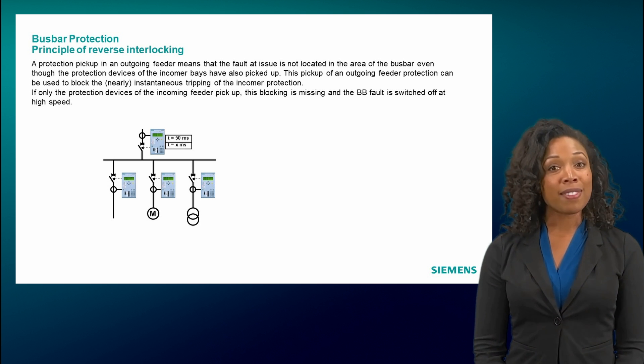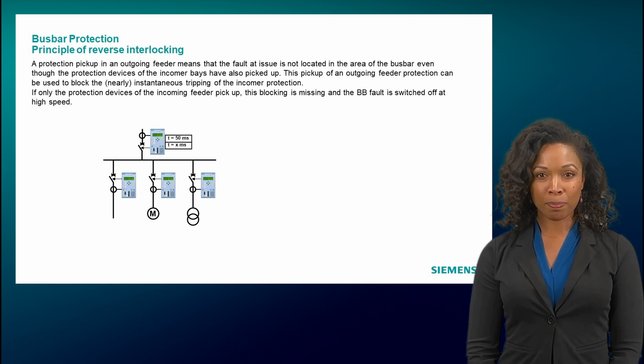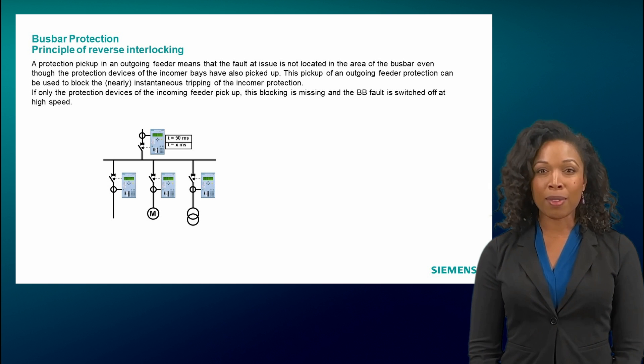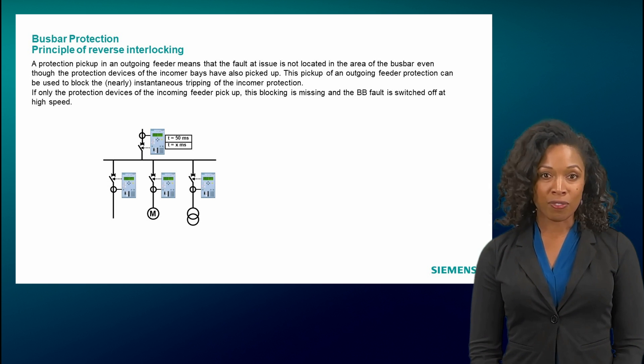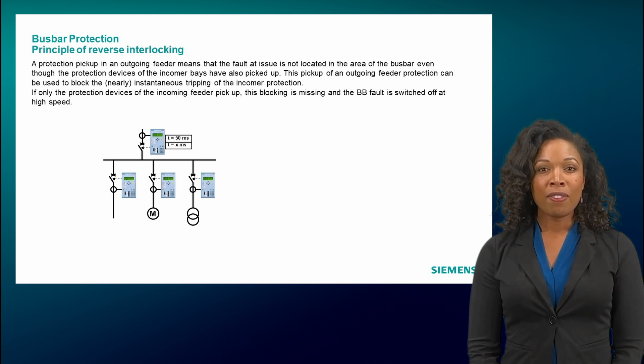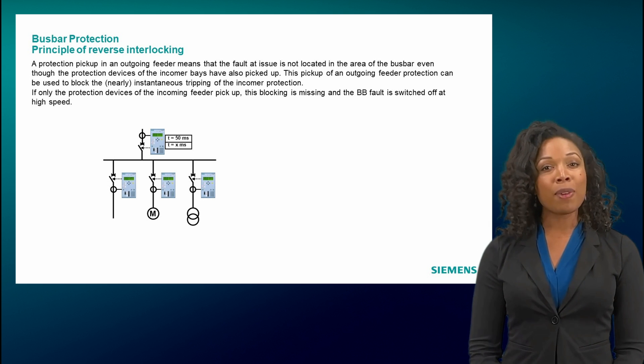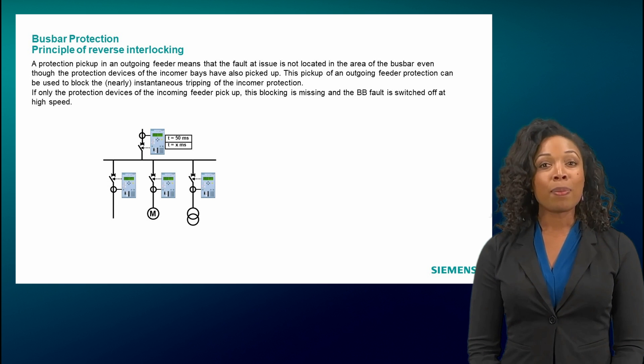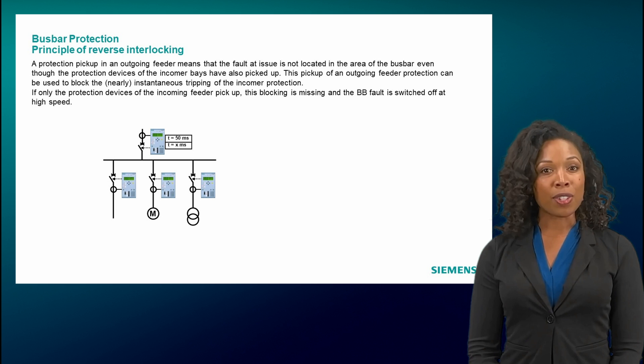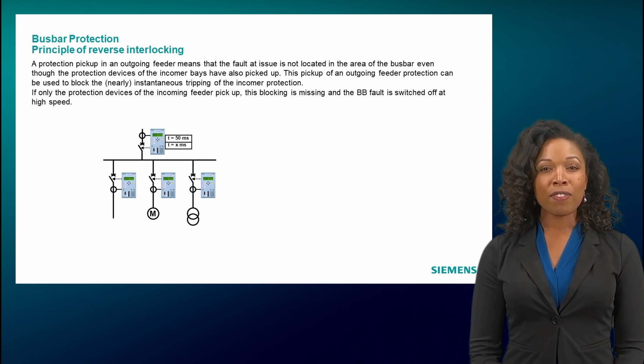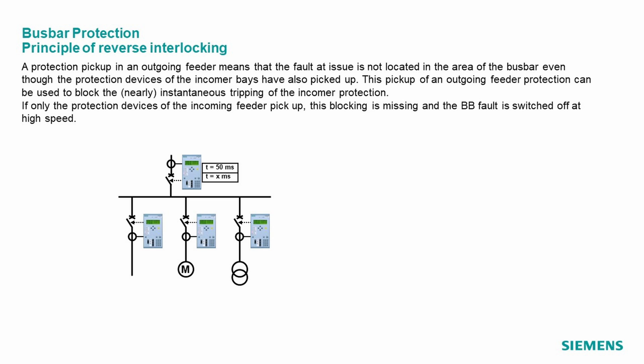For feed-in protection, the two objectives are in contradiction, because the busbar protection requires in the best case an immediate tripping, which would have the consequence that in the event of a fault in the outgoing feeders, a selective tripping of the feeder can no longer take place. Without a reverse interlock, the protection concept will therefore be such that the tripping time in the feed is increased — meaning an increased tripping time is accepted in the event of busbar faults. The contradiction can be resolved by giving the incomer feeder protection information on which it can distinguish whether it is a fault in the outgoing feeder, and therefore the incomer feeder protection is only the backup protection with an increased tripping time, or whether it is a busbar fault with the aim of tripping it as quickly as possible.